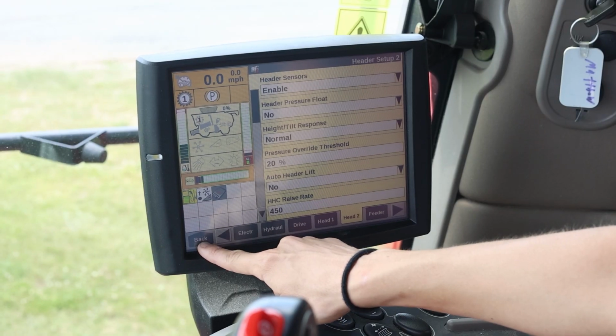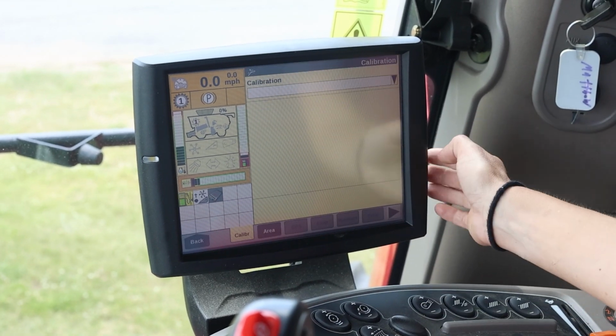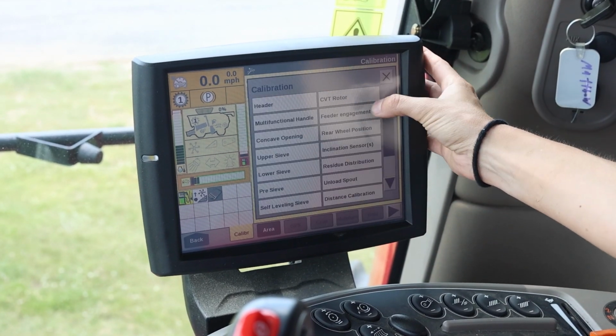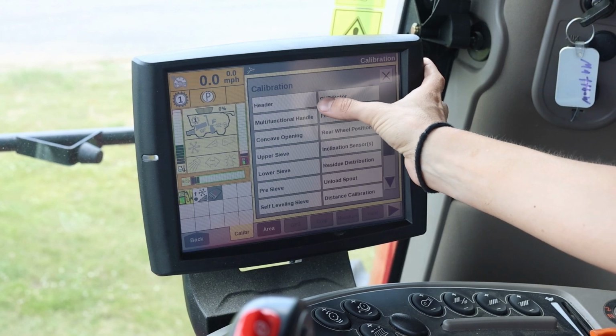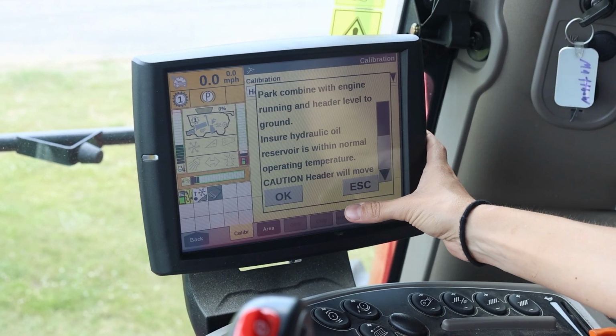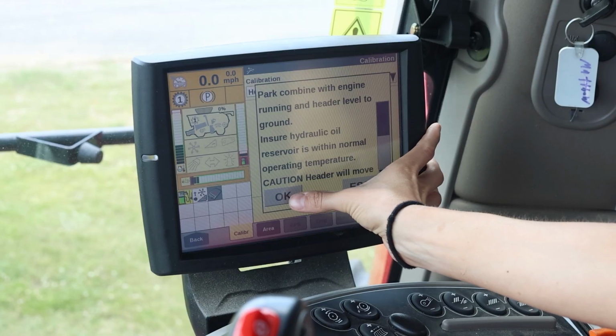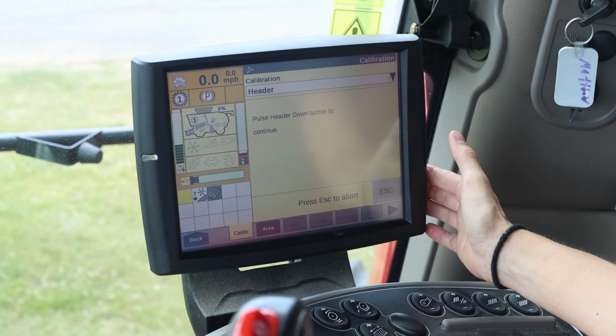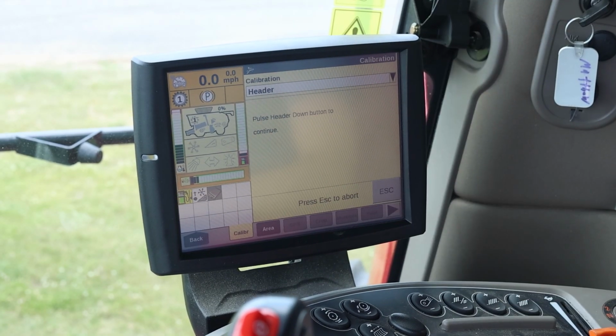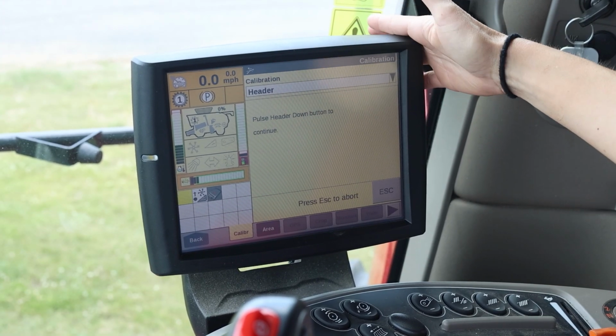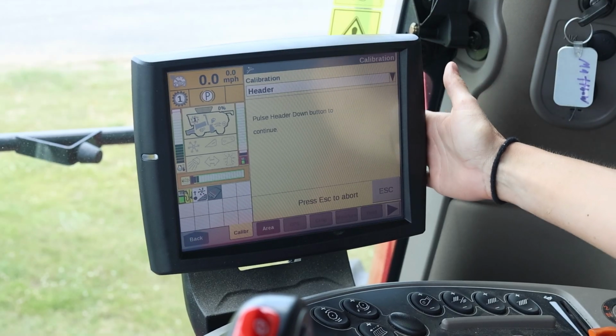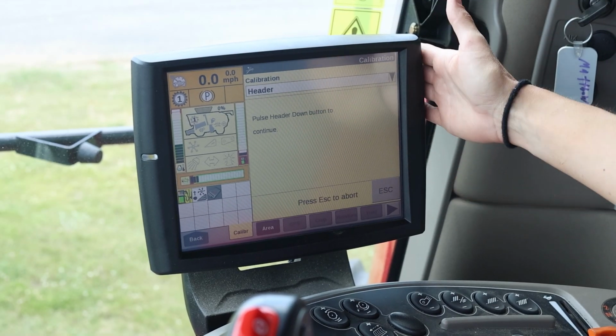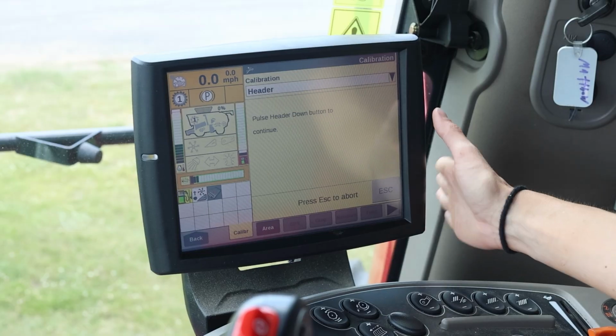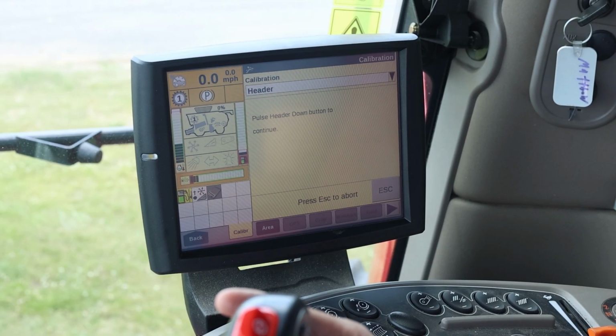Next, we're going to hit the back button and go to calibrations. We're going to perform our header calibration from the drop down, make sure a header is selected, and we'll acknowledge the pop-up, and we're going to perform it. So pulse the header down. The display here does go over the instructions step by step, so we will just follow those on-screen directions. Pulse the header down.